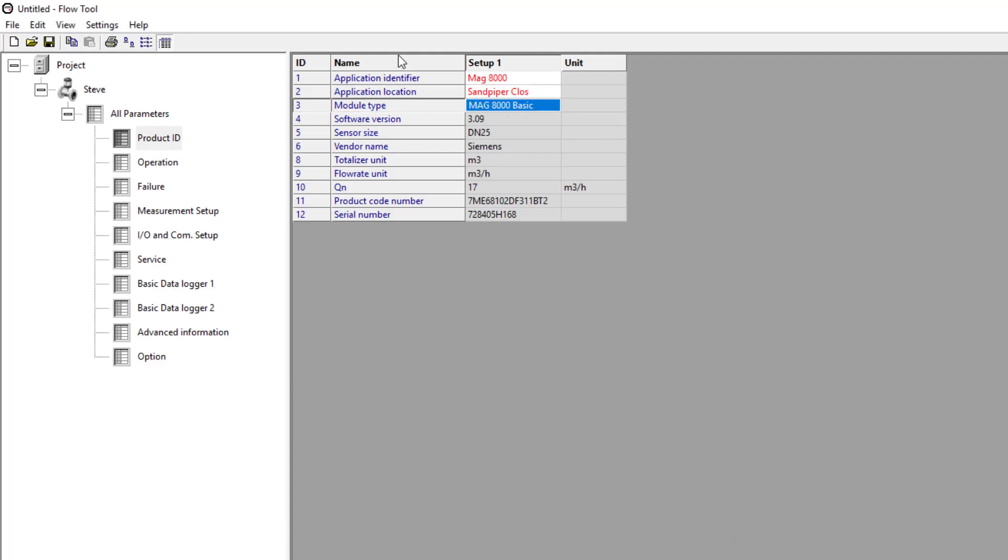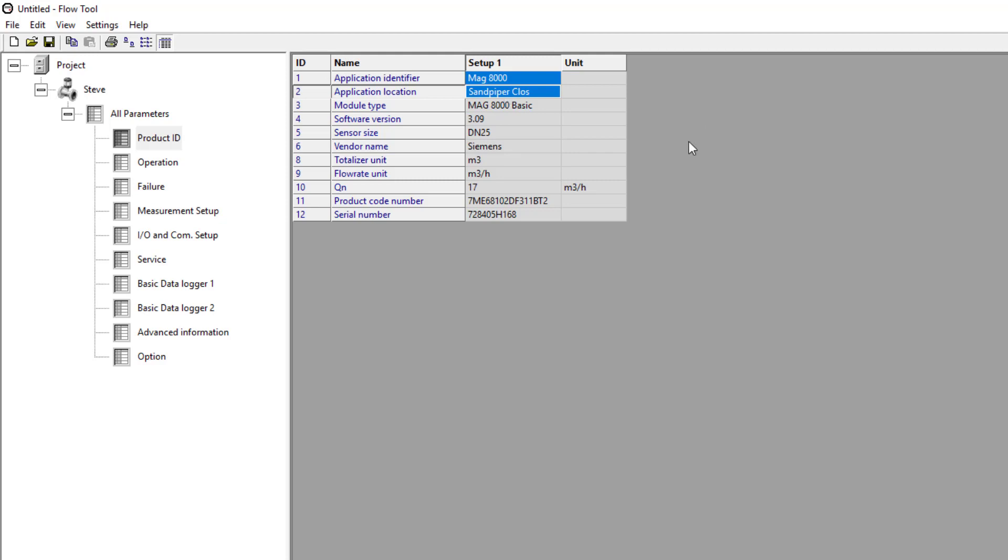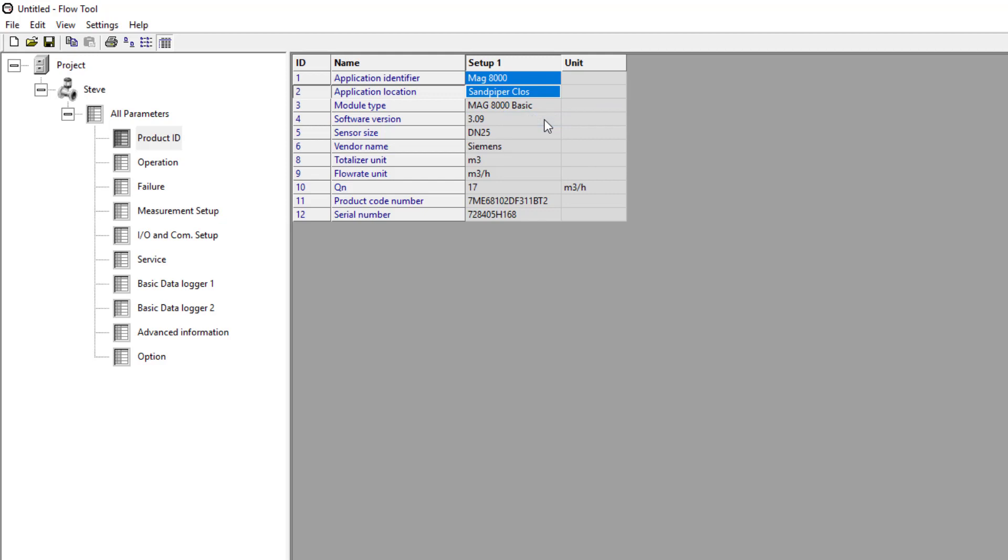It's a very simple software tool and if you think of it as something that just uploads and downloads parameters you can't go wrong. When it's red I've changed it and I need to download that parameter. I can highlight both of those parameters by pressing shift and then clicking, and then I can write selected parameters.